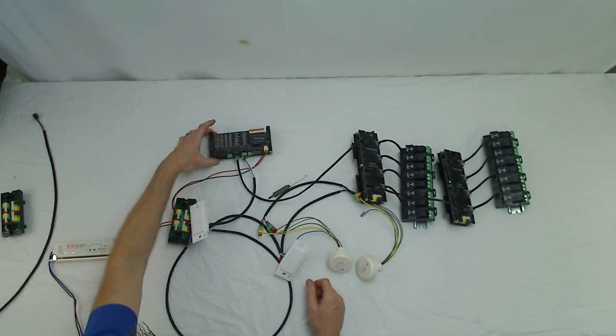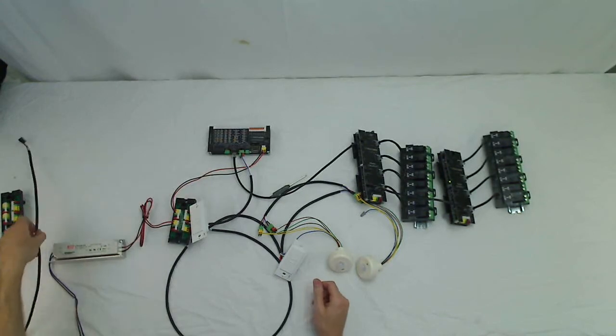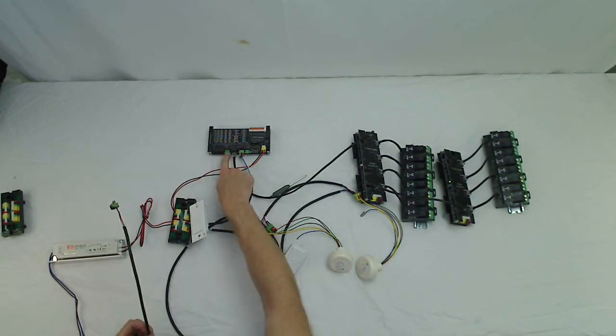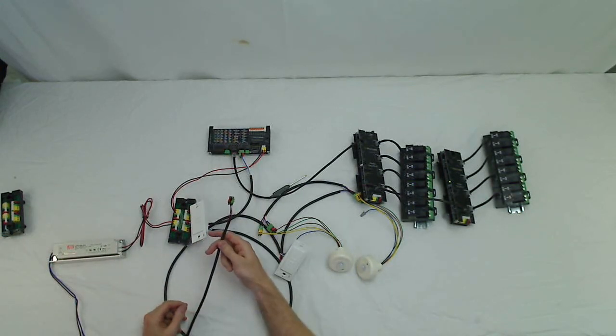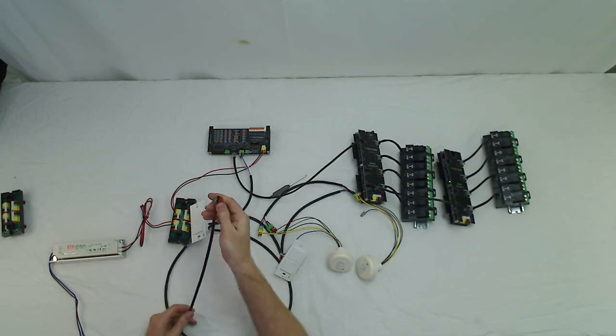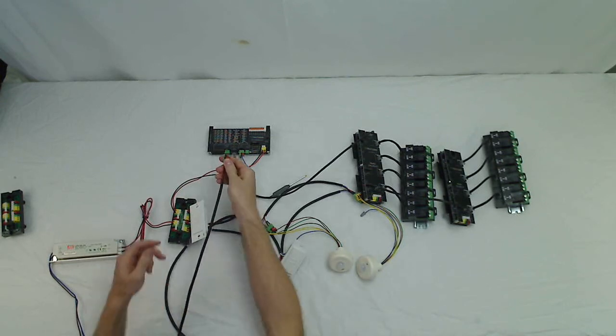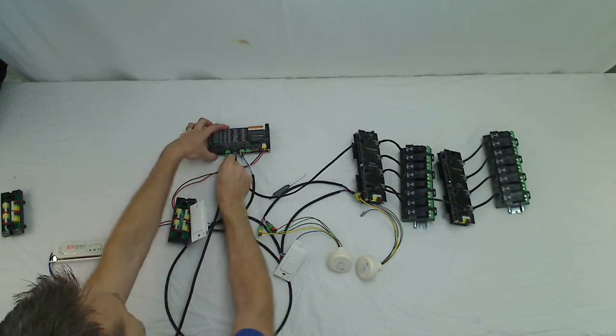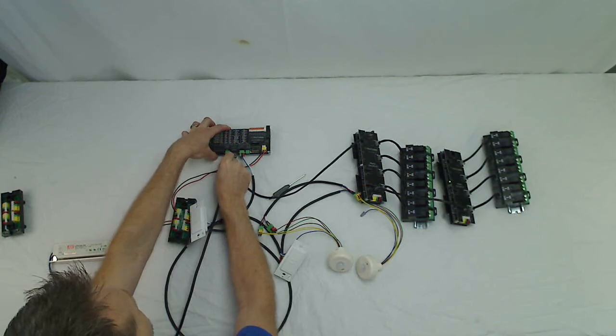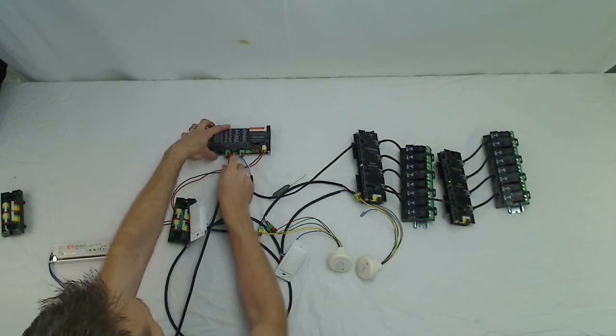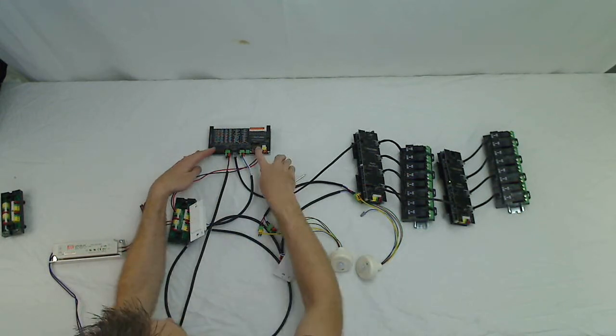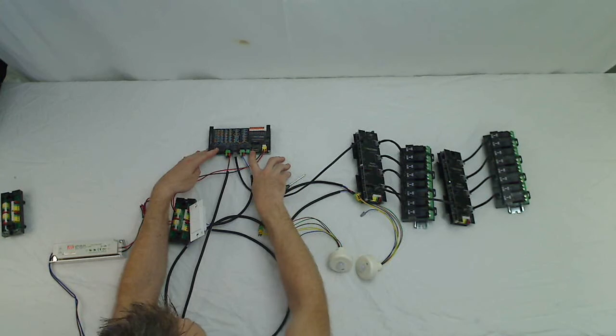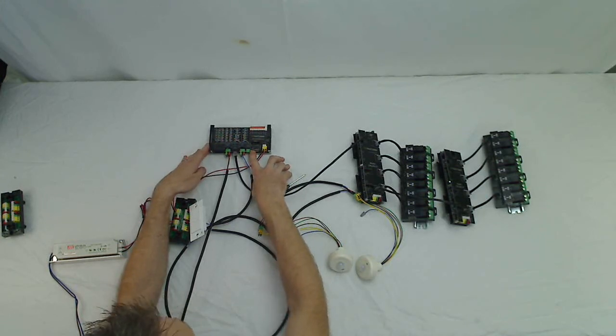So the only other wiring connection is our BACnet RS-485 MSTP connection. And again, it's just a red-black-green connector. So you'll plug in your BACnet MSTP network, and we're pre-addressed at MSTP address number one.